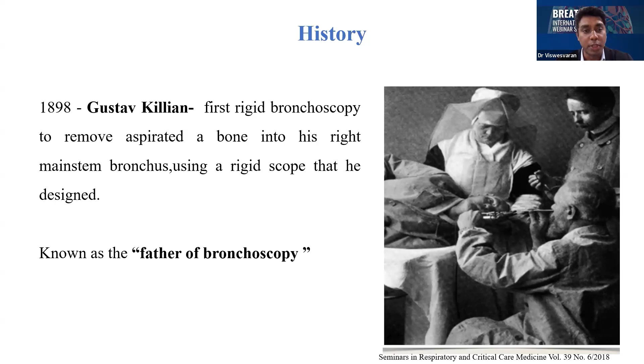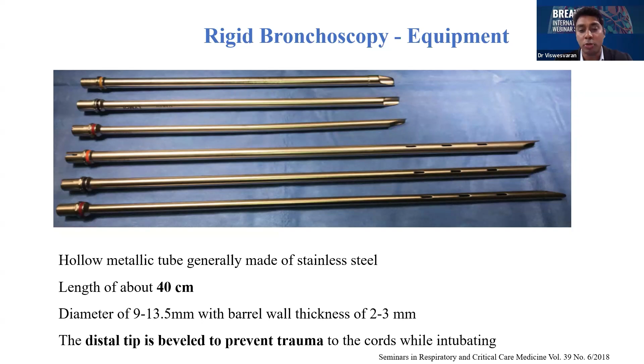Basically, these rigid bronchoscopes are nothing but a hollow metallic tube made of stainless steel. They are about 40 centimeters in length and have a diameter which varies between 9 to 13.5 millimeters, with a barrel thickness of around 2 to 3 millimeters. The important thing about the rigid bronchoscope is that the distal tip is beveled, and this helps to prevent trauma to the vocal cord while intubating.